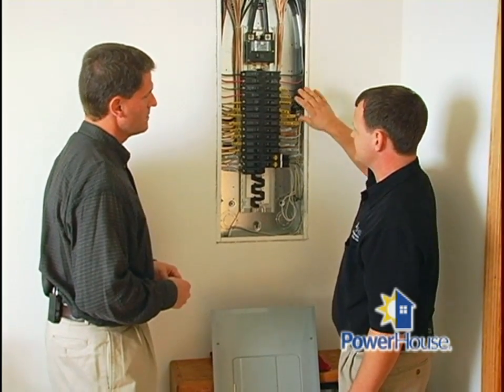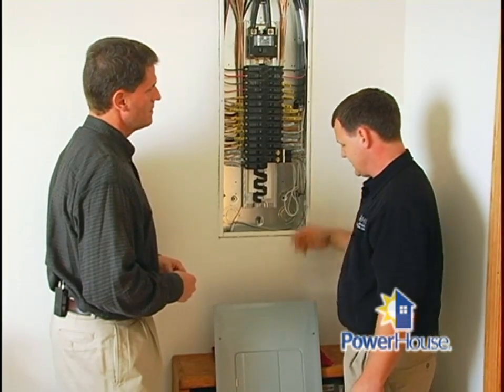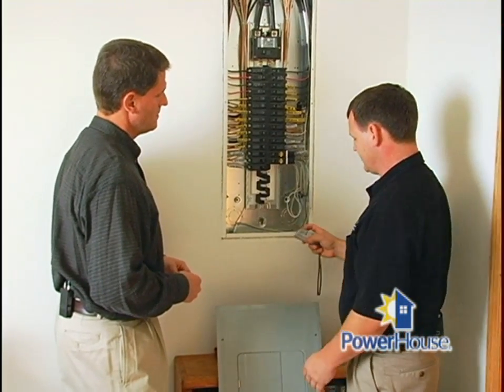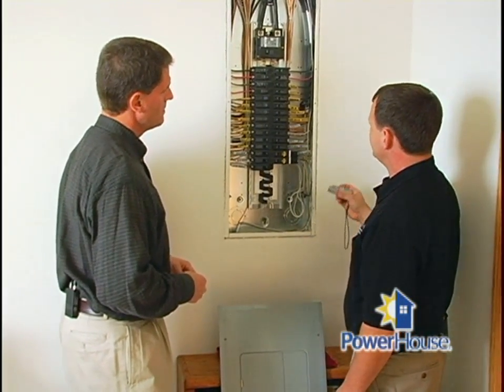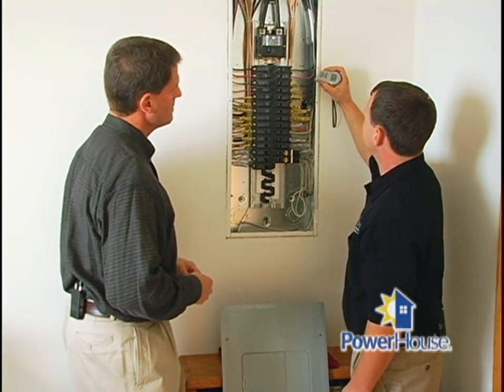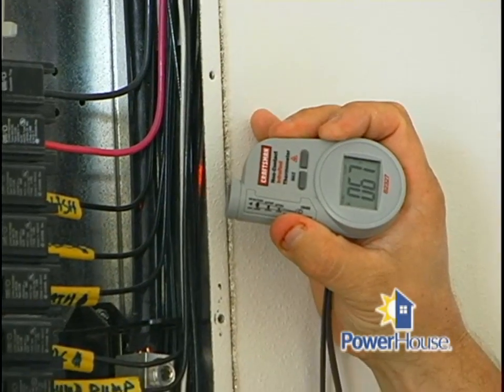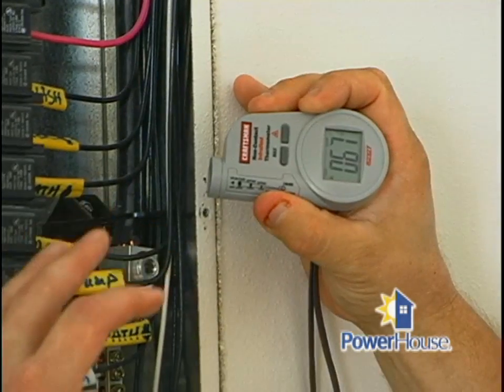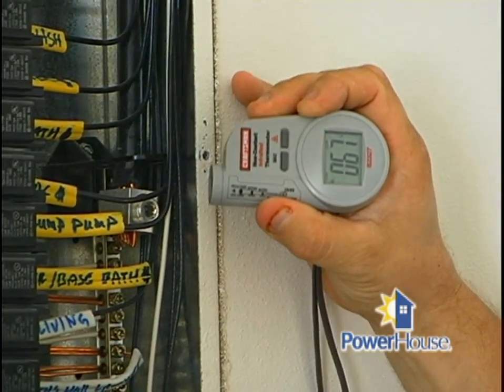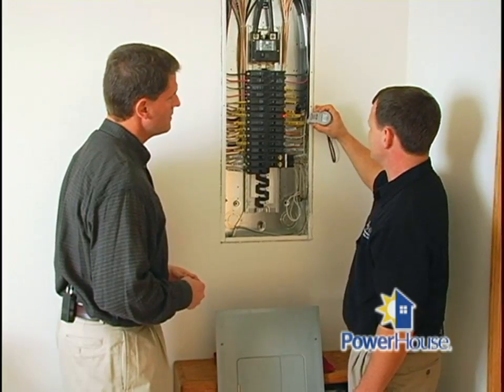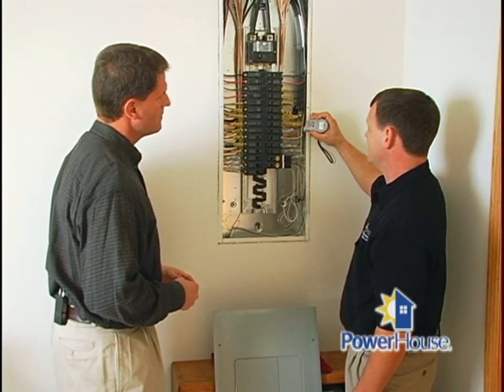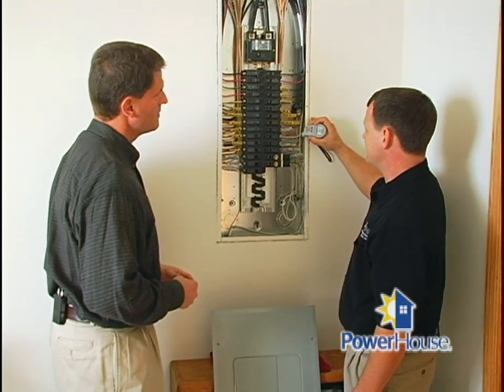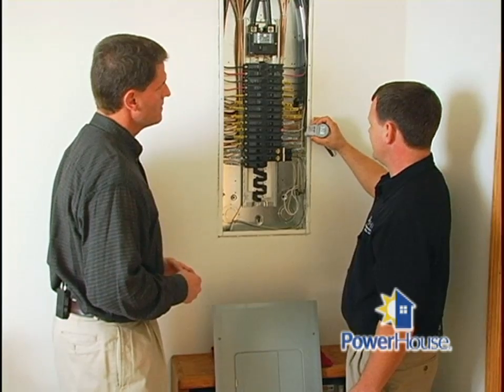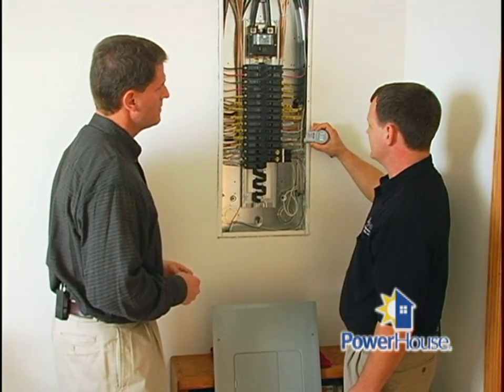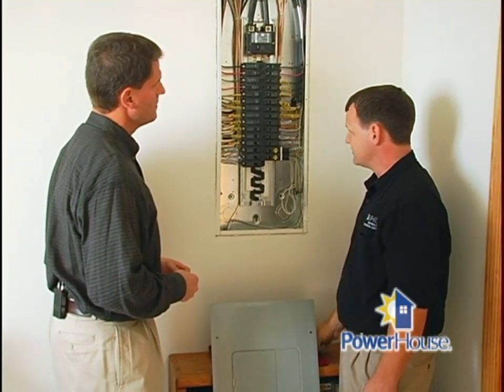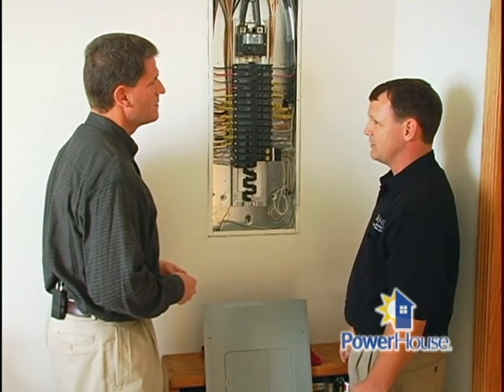The connections are some of the things that we are going to check. We would check the connections to make sure they're tight. We're going to take the time to actually do a thermal check on the panel itself also, by running our little thermal gauge down over all the connections in the panel. We're looking for any kind of drastic temperature change, and I say drastic, and it could be as simple as 5 to 8 degrees, 10 degrees, that can indicate something being loose. Electrical connections and temperature go hand in hand. Where there's one, there's probably the other.